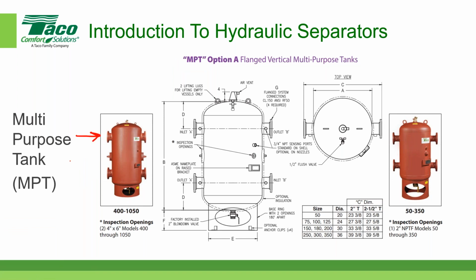Okay, so let's say the left side is the primary side. There's the flow coming in and out. And then say the right side is the secondary side, and there's the flow coming in and out like that. So you can get a multi-purpose tank, which, in terms of traditional multi-purpose tanks, might be a buffer storage tank, or might have a variety of functionalities. But you can also get it configured as a hydraulic separator, and you can add Pall ring baskets in here.